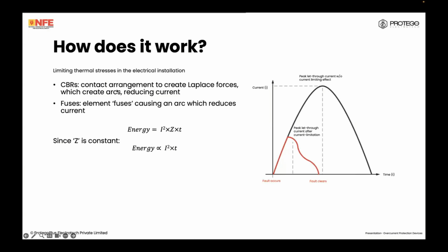Circuit breakers have double rotating contacts which create repulsive forces between the fixed and moving contacts. These are called repulsive Laplace forces, and they cause an arc to be formed. The arc increases the impedance, therefore reducing the current. This happens very, very quickly. For a fuse, the actual fuse element fuses, therefore there's an arc which increases the impedance and reduces the current. That's how the current is limited.